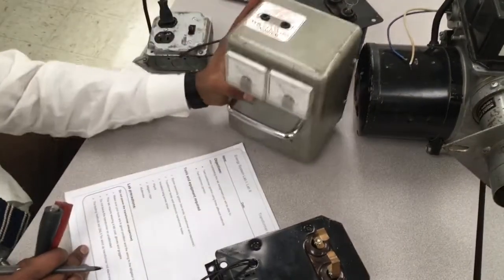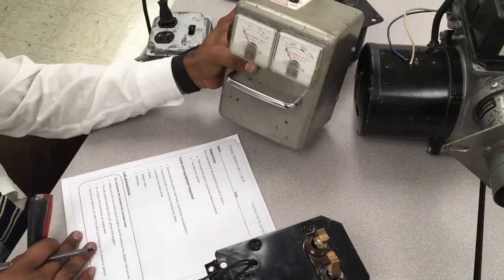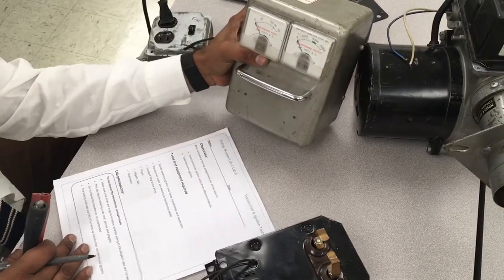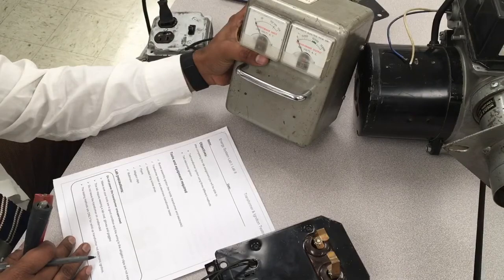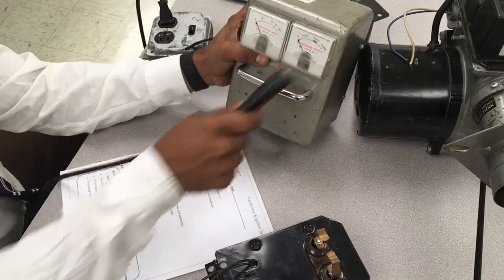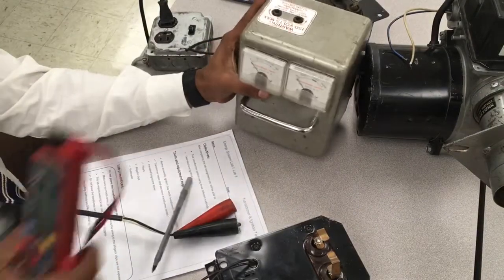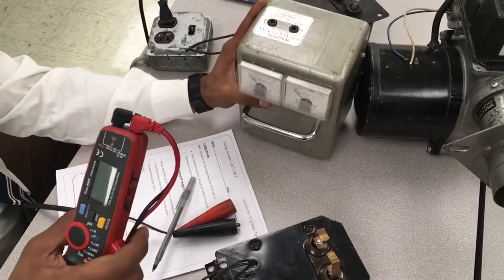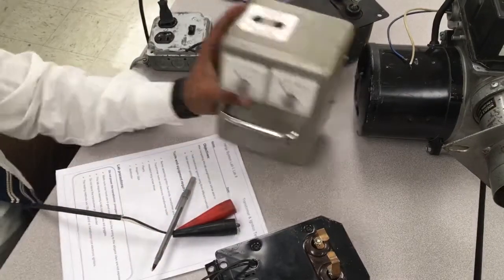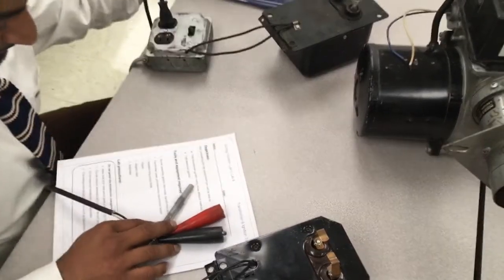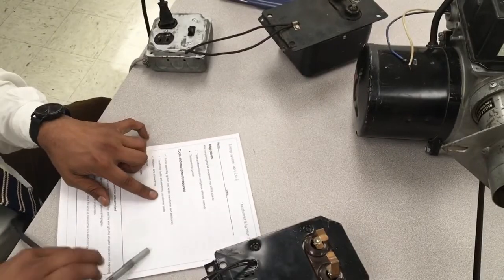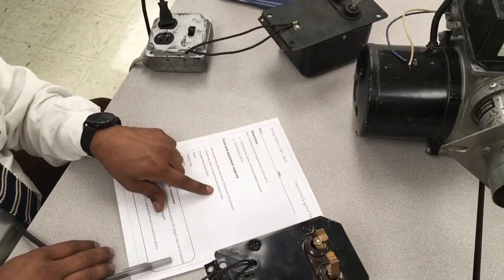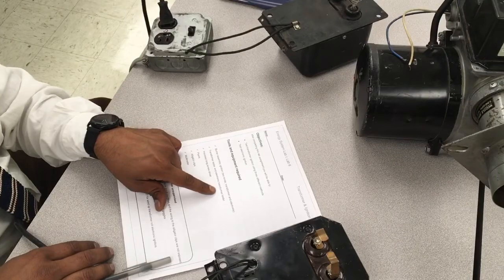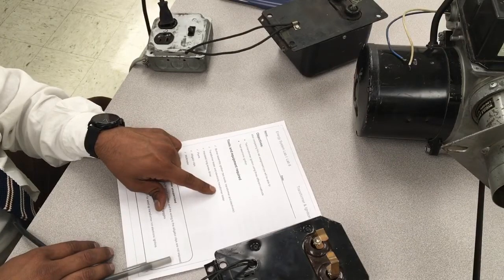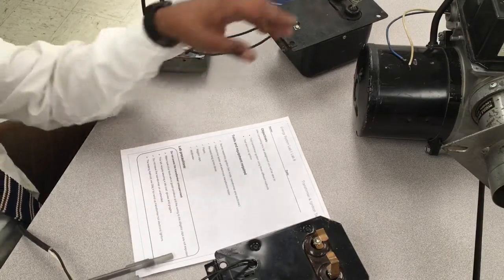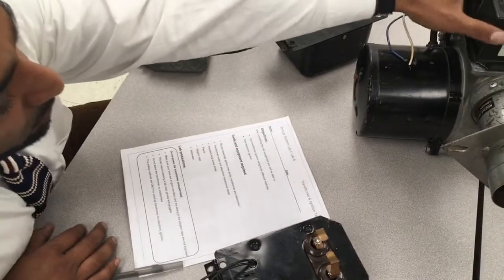If you're going to be working on oil burners for a long time, it's good to invest in one of these because they can measure up to 10,000 volts. These ones are only limited to 600 volts. Any more than that and they will burn. Okay, so that's a tester. And electronic transformer testers, we don't have any of those, and it's good to consult the manufacturer to see what will work. For the electronic igniters, either they work or they don't.